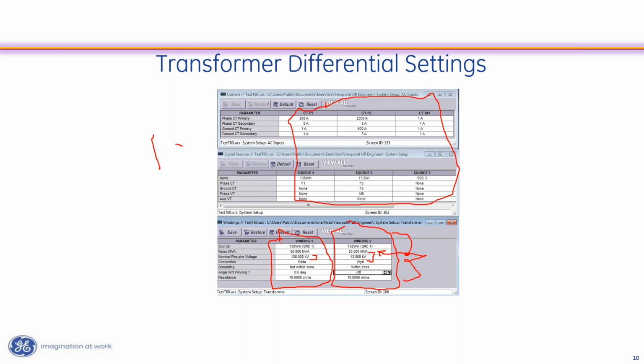So what that means is if I have 10 amps flowing into the 138 kV winding, it's going to take that magnitude compensation factor and multiply it times that current. So now I have 100 amps, which is exactly what I have flowing out of the 13.8 kV winding.